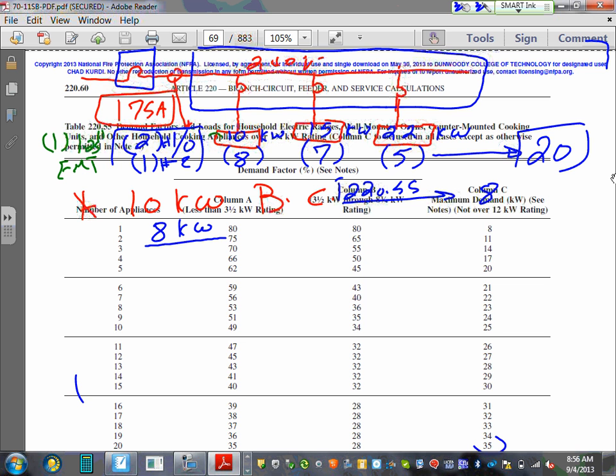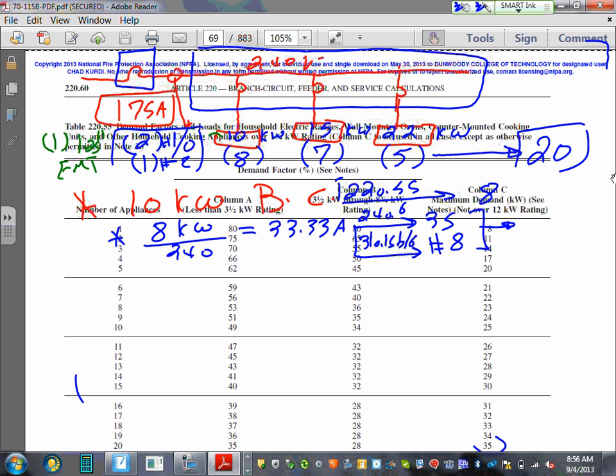8 kW divided by 240. And can somebody give me the answer, please? 33.33 amps. And we're going to go to 240.6. That will get you 35. And also the table 310.15(B)(16) will get you number 8. Number 8, and we said because there is a restriction on this size, it has to go 40 and what? And number 8, 2 conductors number 8. 40 and 2 conductors number 8.